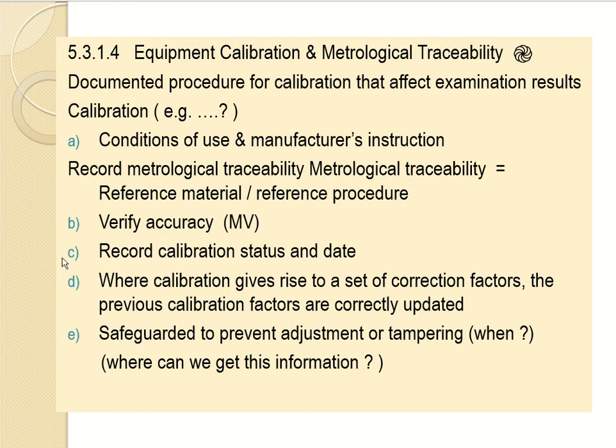Record calibration status and date given by the manufacturer, where calibration gives rise to a set of correction factors, the previous calibration factors are correctly updated. Yeah, this one should be monitored and recorded. Safeguarded to prevent adjustment or tampering. Usually this one can happen when the manufacturer does the preventive maintenance on the machine, when they adjust the setting of the machine, or when we adjust the setting of the analyzer. So we need to have documents to prevent this adjustment happening without us noticing it. So where can we get this information? It is from the manufacturer manual instruction.